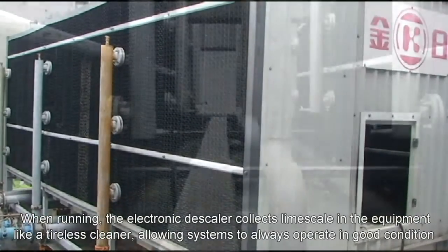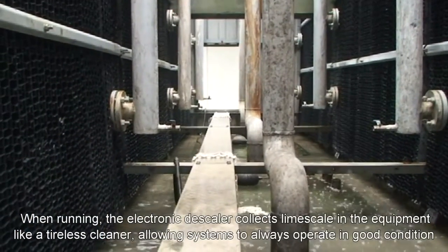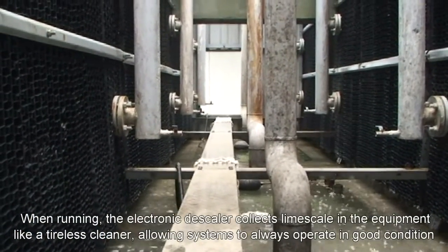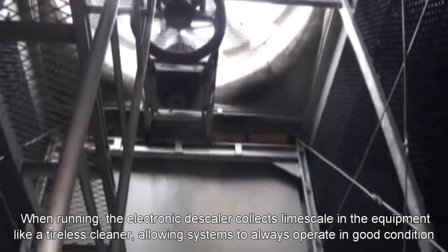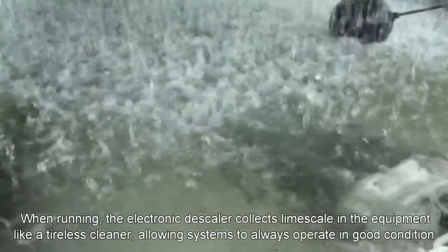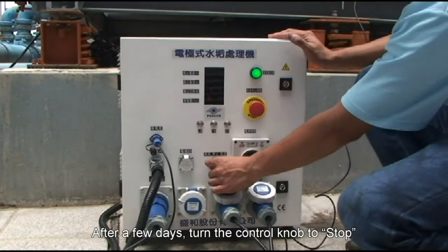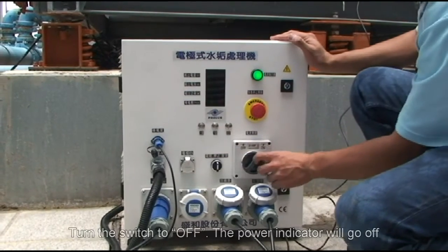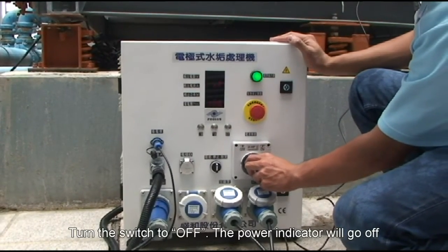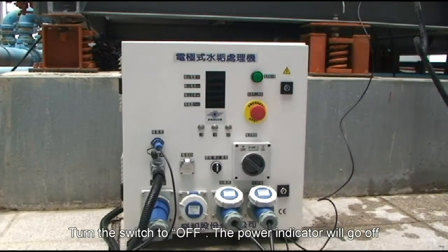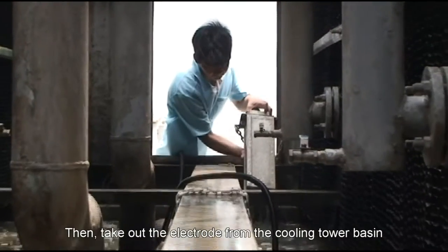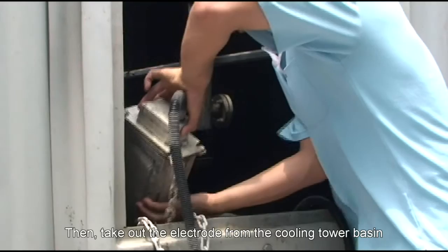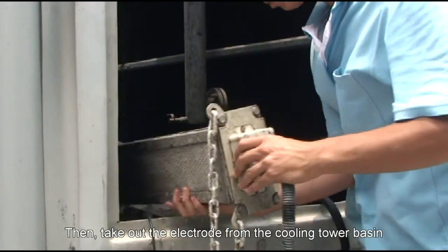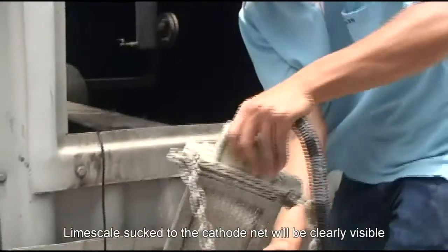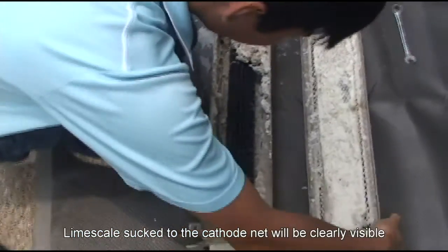When running, the electronic descaler collects limescale in the equipment like a tireless cleaner, allowing systems to always operate in good condition. After a few days, turn the control knob to stop. Turn the switch to off. The power indicator will go off. Then, take out the electrode from the cooling tower basin. Limescale sucked to the cathode net will be clearly visible.